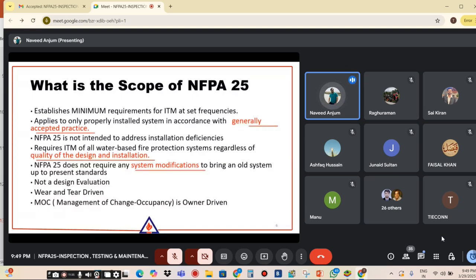This is important. Sometimes inspectors think, and owners also think, that the inspector will also tell us about the deficiencies of the system. No, it is not part of NFPA 25. The inspector assumes that every system is installed as per design and everything is okay. He just has to verify, through inspection, testing, and maintenance, whether the system is working or not. Design deficiencies are not related to inspections. NFPA 25 requires ITM of all water-based fire protection systems regardless of the quality of the design and installation. It does not require any system modification to bring an old system up to present standards, and it is not a design evaluation. Wear and tear is owner driven, and MOC, management of change in occupancies, is the owner's responsibility.